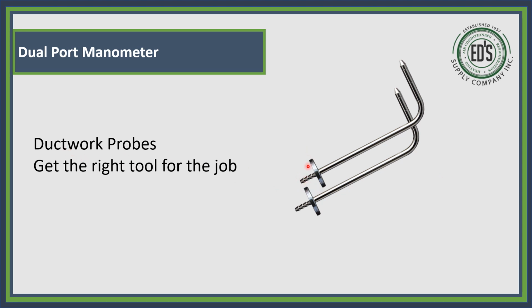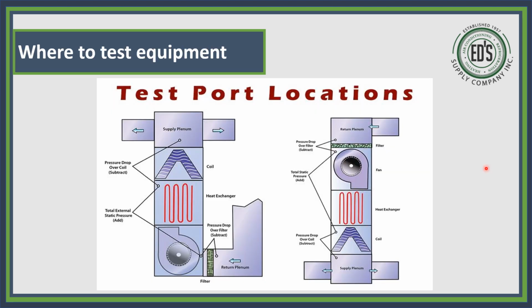So these are the duct probes that we were talking about. They're magnetic here. And on the face of that, there's an arrow that lines up with this probe. So there's an arrow pointing this way because that probe is pointing that way. You'll drill a hole in the ductwork, this will go in, and there's a magnet here that will snap to the ductwork. And you point the arrow, which is facing the same as that, into the airflow. Your tubing goes here and goes into your dual manometer.